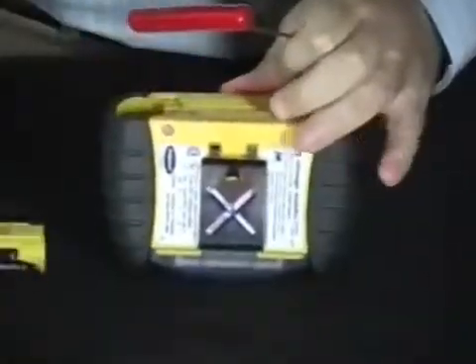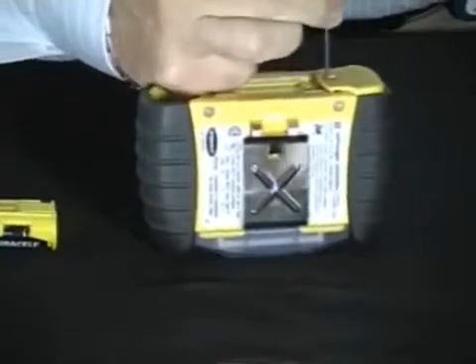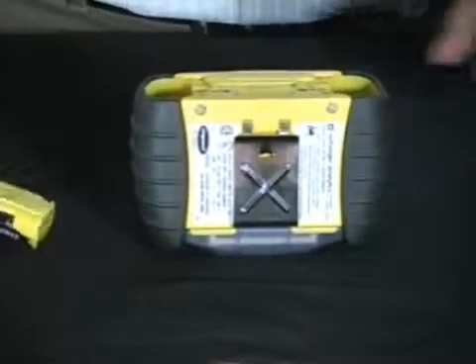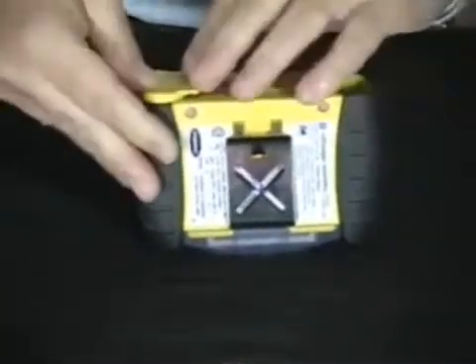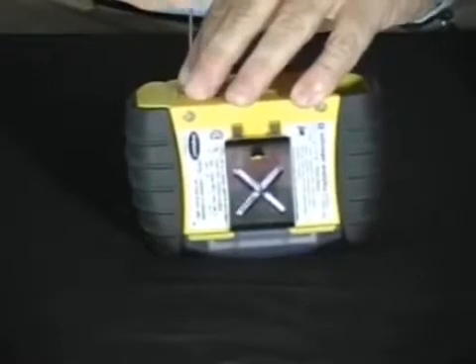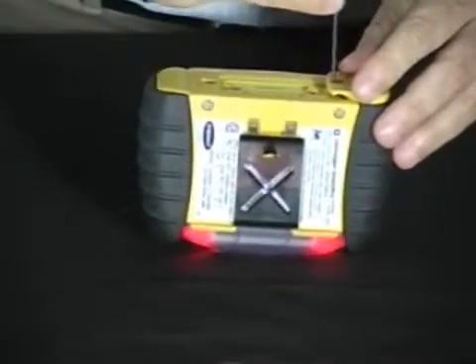Battery replacement. To replace the batteries, use the allen head screw that comes with the instrument to remove both battery pack compartments. For alkaline batteries, replace the batteries and install the battery pack back into the instrument. Turn the monitor back on to confirm battery installation.